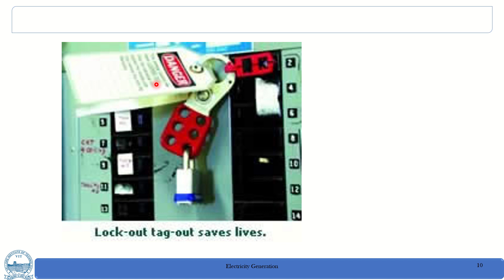And then confirm. Once you break the supply, we should ensure further that no part of the circuit is energized and it is completely switched off in the particular work spot or the area where you are working. The confirmation provides additional safety for the personnel, and it can be performed in the following ways. We can physically inspect to see all the 3 contacts are completely open and there is no partial closing, and we can listen for a humming noise from the transformer.